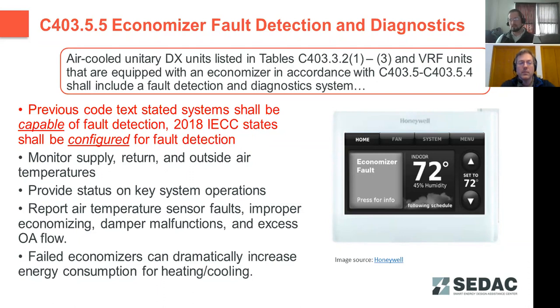What you see here in the image is an example for a small DX system that has an economizer installed on it. Say it's a residential unit with an outdoor air damper connected to the return. It just has a readout on it for that economizer damper in that outside air duct to that furnace that reports whether there's a fault or not. It highlights that screen. You press on that screen and it tells you whether it's a sensor error or should be economizing and not. So that's one compliance method.